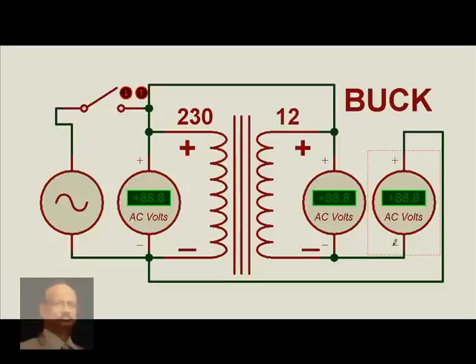Similarly for the buck operation, we have an arrangement here again in series, but here the plus is connected to plus and minus to minus. In the process, the voltage is definitely reduced. And when we switch this on, we find 230 volts, 12 volts minus, and 218 volts that we get. This is how the buck-boost of the voltage in a transformer happens, and that is the basic principle of a voltage stabilizer.